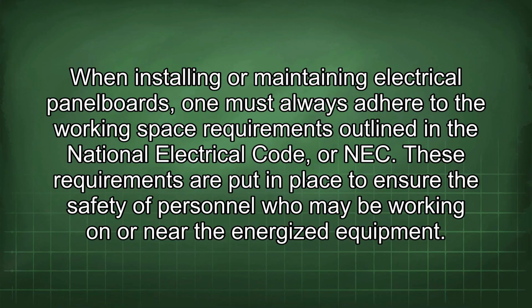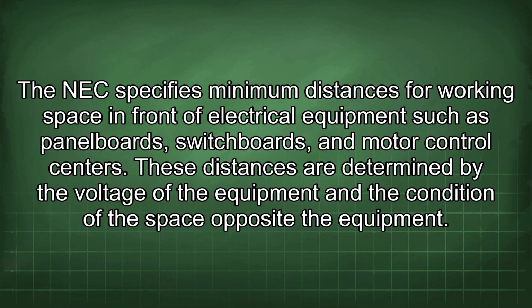When installing or maintaining electrical panel boards, one must always adhere to the working space requirements outlined in the National Electrical Code, or NEC. These requirements are put in place to ensure the safety of personnel who may be working on or near the energized equipment. The NEC specifies minimum distances for working space in front of electrical equipment such as panel boards, switchboards, and motor control centers.